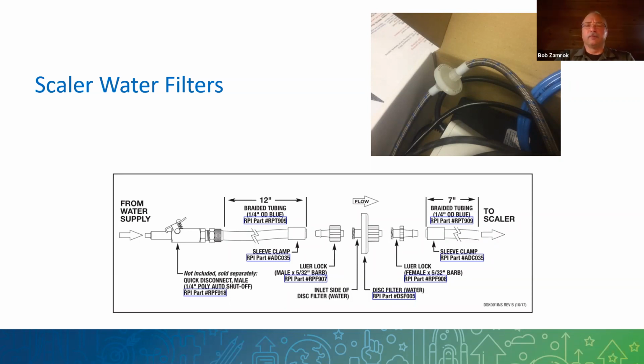One of the vacuum pump manufacturers that recommends a Slug Buster type product is Ramvac. When we replace a wet ring pump with a dry system like a Ramvac, the first time they do that you'll get a lot of debris coming through, and you need to watch your filters then. So it's not a bad thing - you're getting stuff out of the lines.